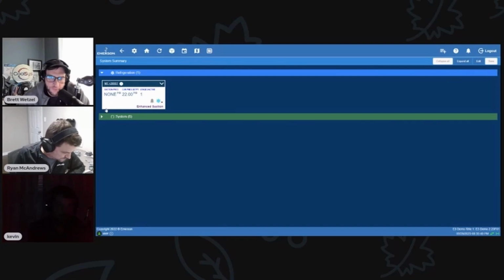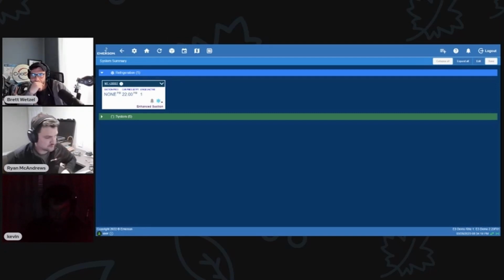Do you have to configure the input first before you link it to the application, or can you do the same thing you used to be able to in the E2, where you can basically name it and then it'll take on the characteristics of what it's programmed for? Yeah, exactly. I'll do it after with a circuit or something like that. You can either pre-configure the inputs, or you can create your application. Then if you associate to a board and point that hasn't been configured yet, as you select that point, it's going to pop up analog, digital, the same thing we went through before.